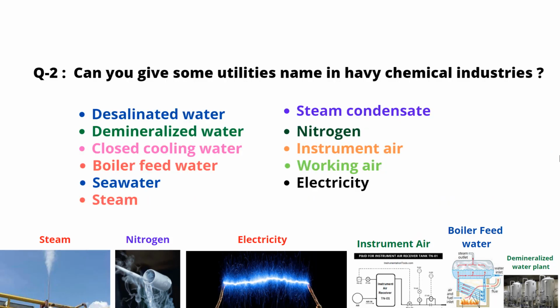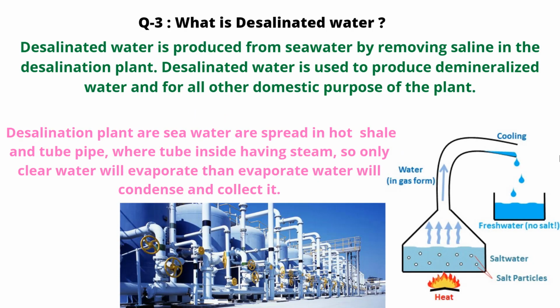Can you give some utility names in heavy chemical industries? Desalinated water, demineralized water, closed cooling water, boiler feed water, sea water, steam, steam condensate, nitrogen, instrument air, working air, electricity, etc. What is desalinated water? Desalinated water is produced from sea water by removing saline in the desalination plant. Desalinated water is used to produce demineralized water and for all other domestic purposes in the plant.